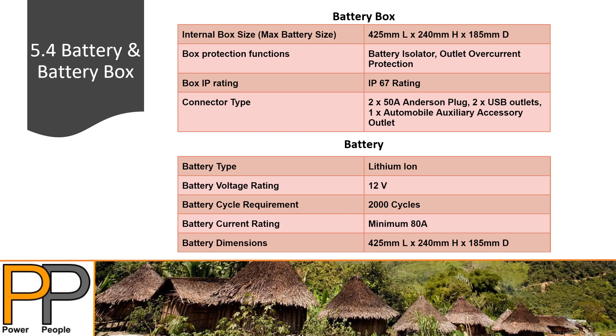All right, cables and connectors. So we have asked for 6mm cables. This is just to account for any potential for voltage drop we have over the system. Insulation XLPE. This is a 2-core and sheath type cable. We have a requirement for differently identified cores using red and black coloring for each of the cores, that is. The cable connectors, MC4 at the solar panel end and 50 amp Anderson plug at the battery box end. This is obviously due to the polarity sensitive nature of an Anderson plug. Weatherproof covers to be installed over the end of the Anderson plugs. The cable protection is to be 25mm heavy duty conduit.